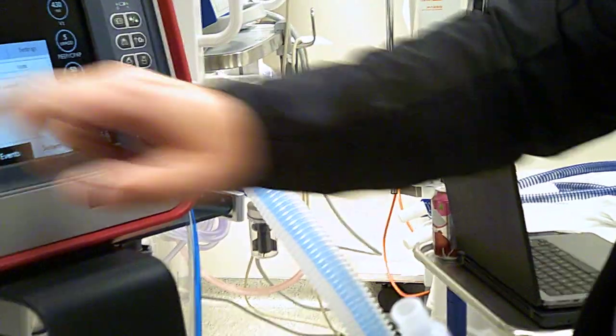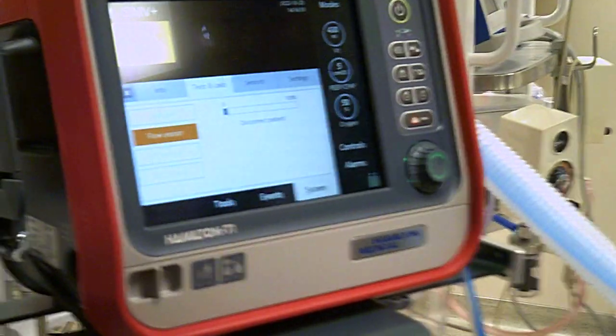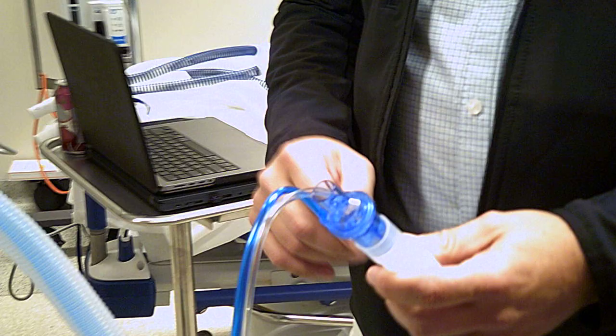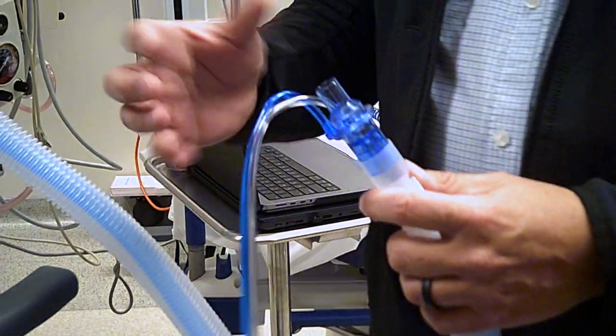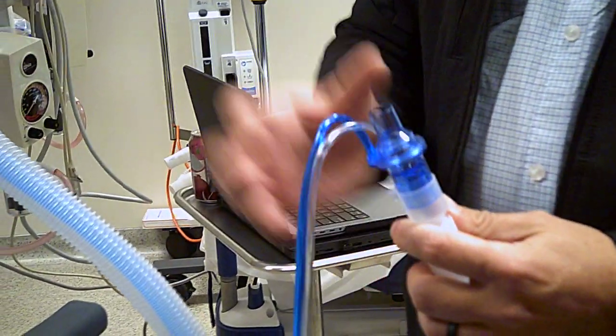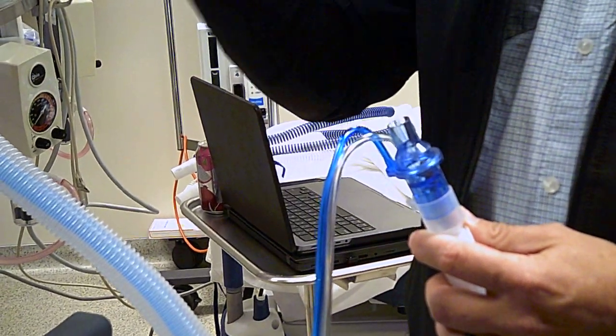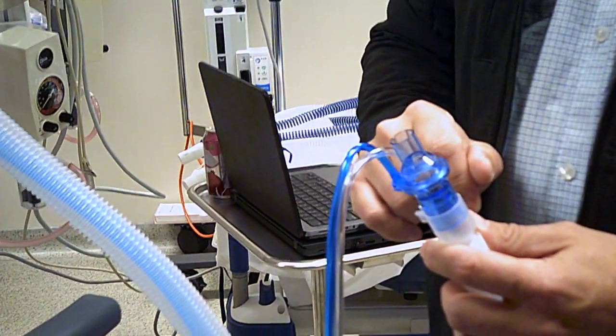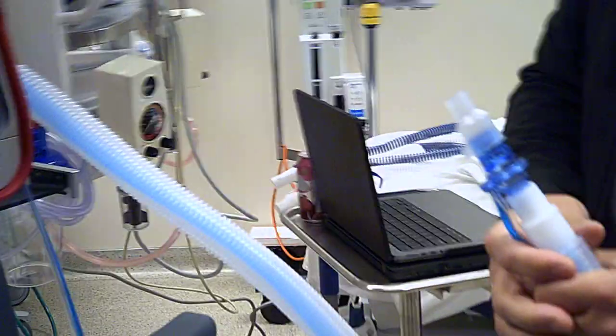The next is going to be the flow sensor. So that's when we absolutely need this white piece. It says disconnect patient, flip flow sensor. So you're going to do the whole blue and flip it over. Now this is when people start talking and they're like, ha ha ha. You can also use the noise because it will start getting up really high, and when it gets to that highest pitch, it's going to automatically tell you to flip it again. But see, if we're here talking and I'm not paying attention, look, I knew right away because that noise went away. So you flip it again. It's going to do the same thing, and then we should be done.